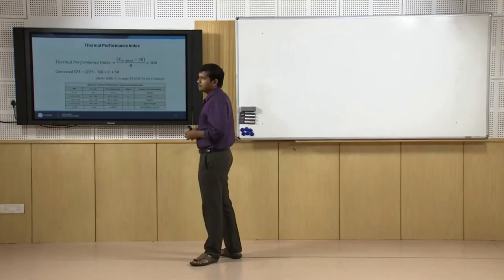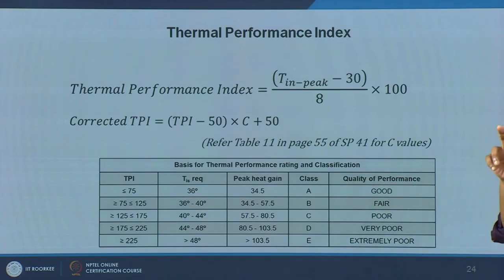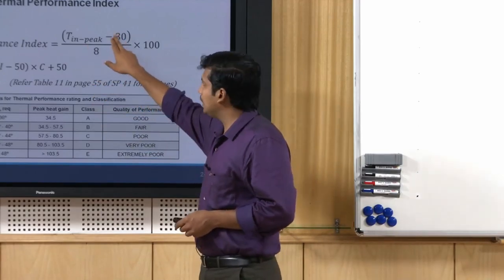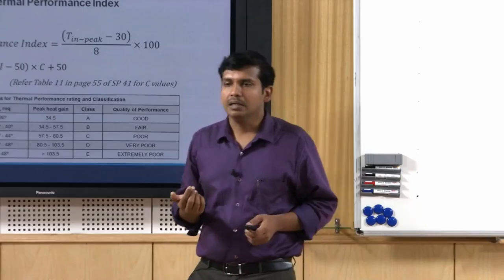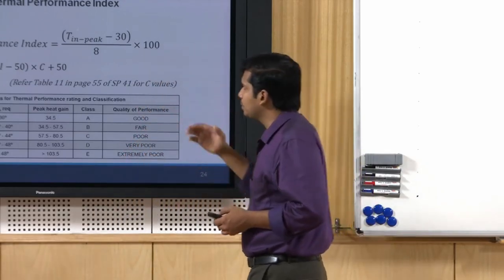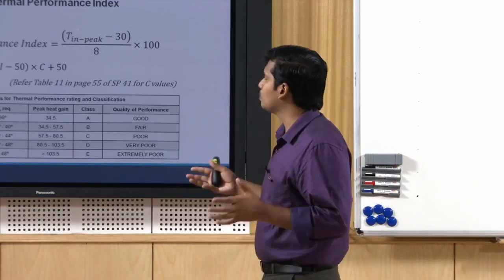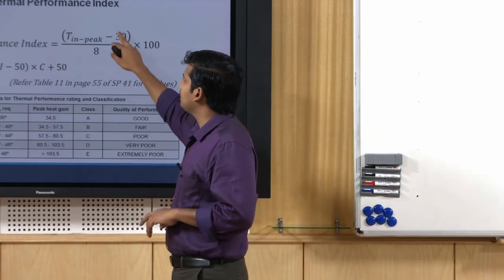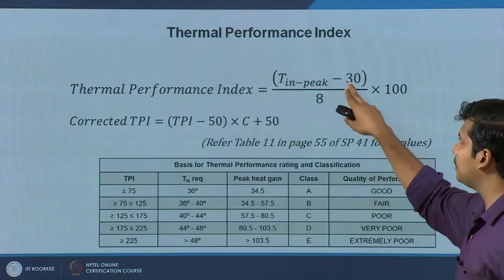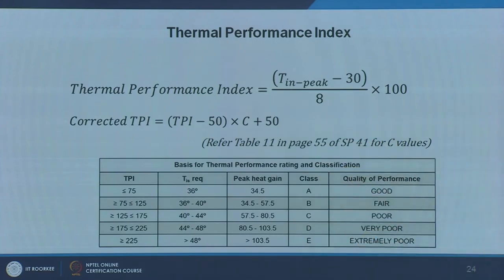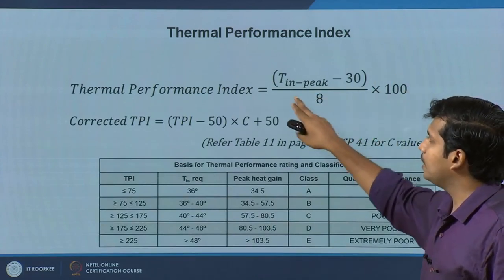The next indicator is the Thermal Performance Index (TPI). This equation gives T_in_peak — the inside peak surface temperature. For example, if peak surface temperature goes to 35 degrees: (35 minus 30) divided by 8, multiplied by 100. The value 30 comes from a series of calculations accounting for maximum heat gain for a specific wall system with a given fenestration area, representing the maximum comfort temperature. The value 8 reflects that when wall surface temperature rises above 30 degrees by 8 degrees (to 38 degrees), discomfort begins.